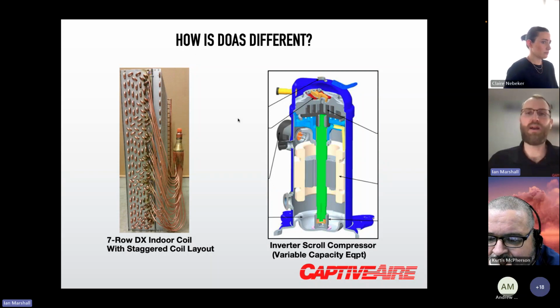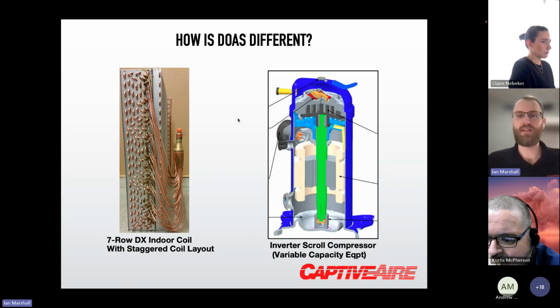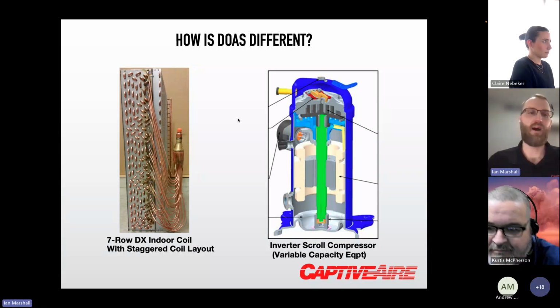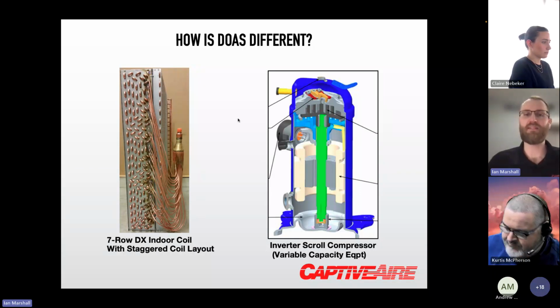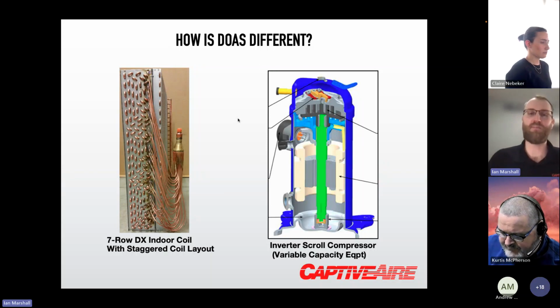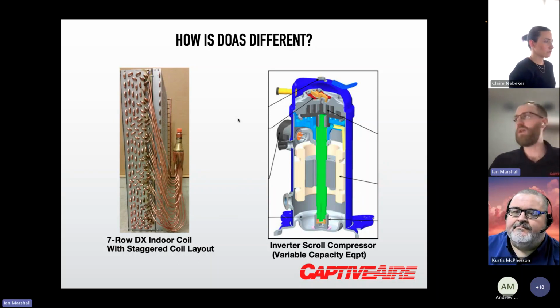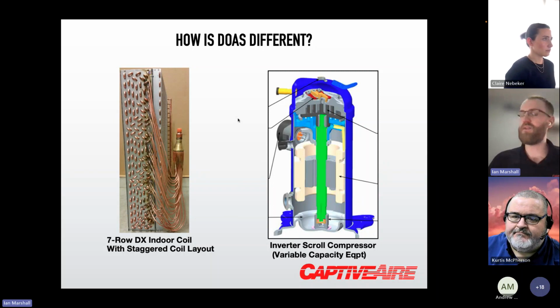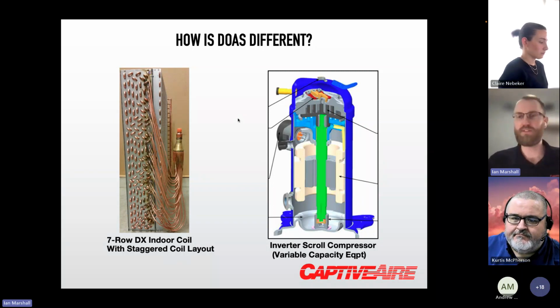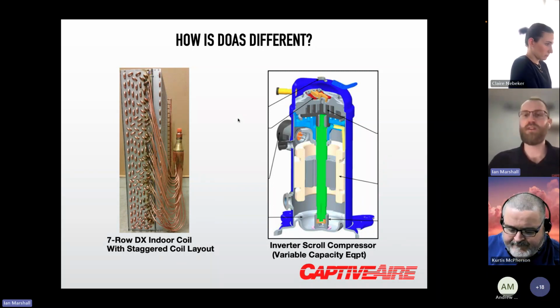Obviously with DOAS design, you're designing around the peak design condition, which happens maybe a few days a year. And you need to be able to accommodate and hit the required leaving air temperatures at that peak design condition. But the vast majority of your operating time is at a swing season day or a more mild condition. So we standardize with an inverter scroll compressor, which is a true variable speed compressor. So it has modulating capacity.